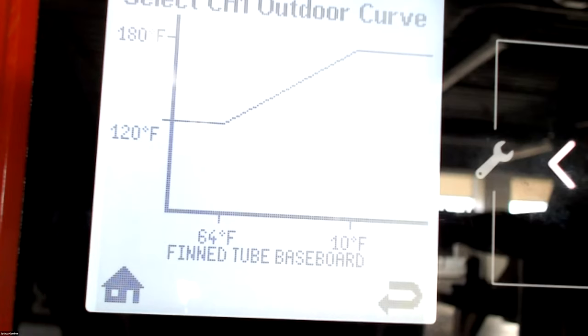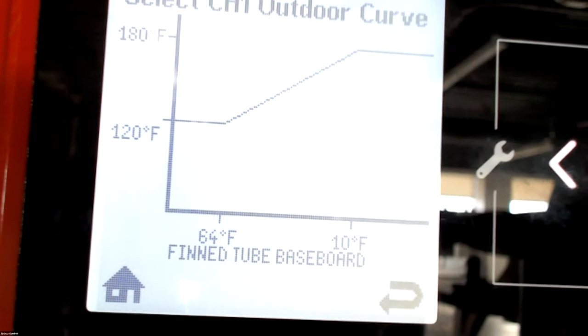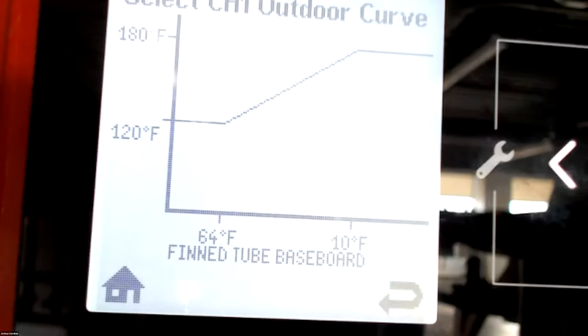And also, I'm going to take my 10 degree temperature, cold weather design, and I'm going to adjust that to 30. That means that when it gets 30 degrees outside, I'm running at full potential as opposed to 10. So if I have a 160 to 180 curve that's at 10 degrees, when I'm at 30, I might be running at like 170. So we want to have a heating curve where we're saving some money, but not to the point where the homeowner notices a lack of heat. And that's where we got to find that balance. If you're doing radiant, most times you're going to be using a LoopCAD or a system design, and you're going to have those temperatures that you can dial this thing into.